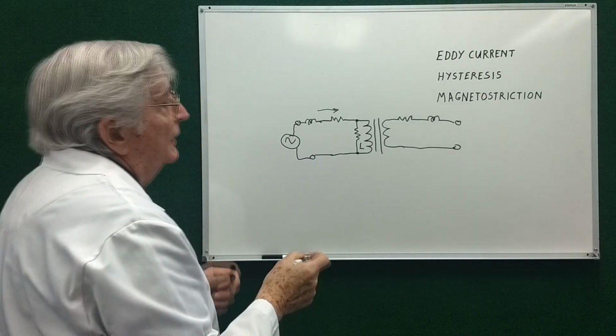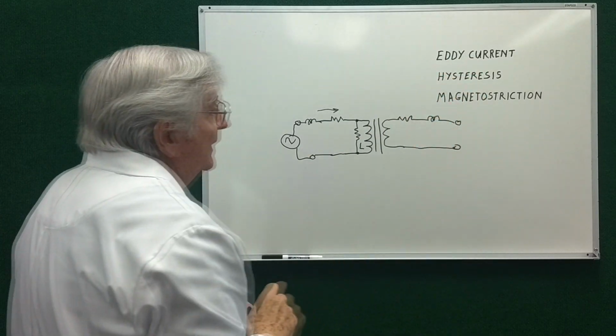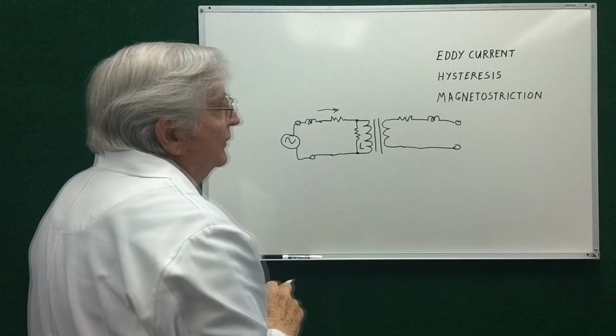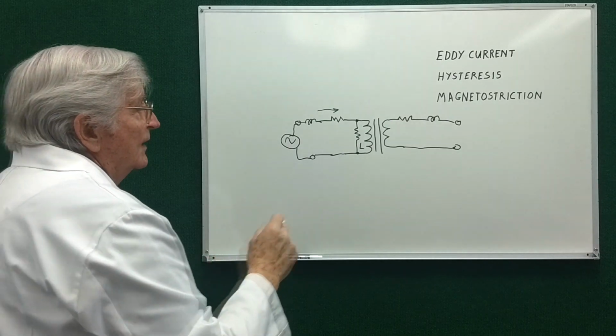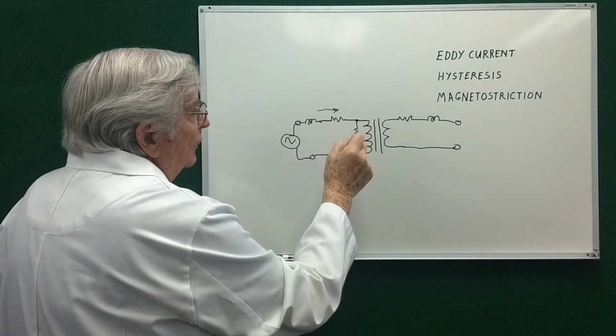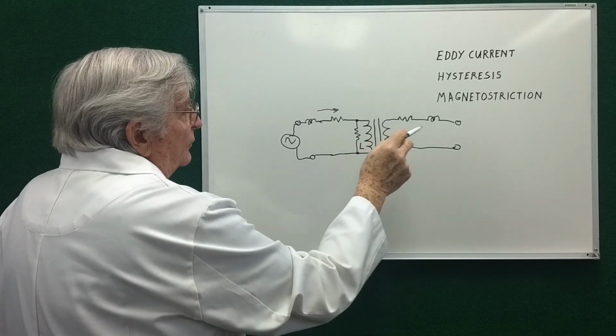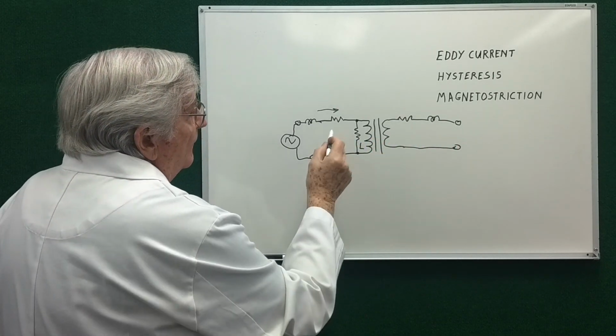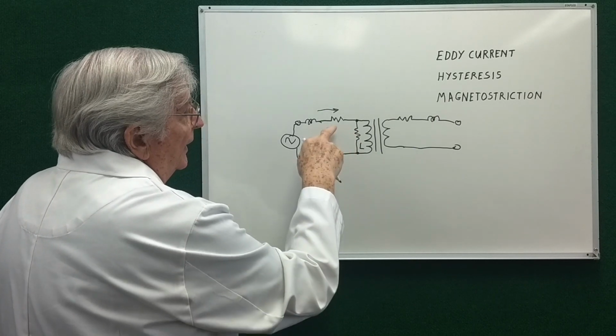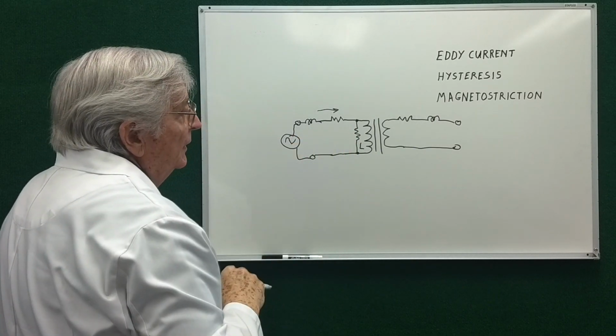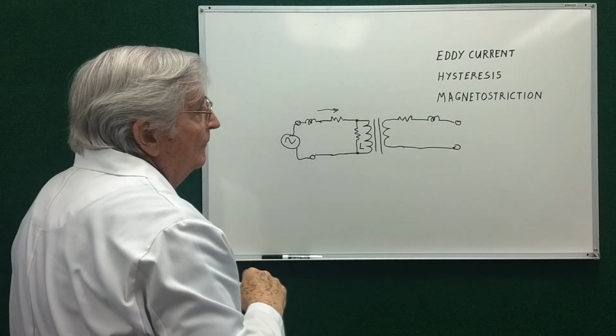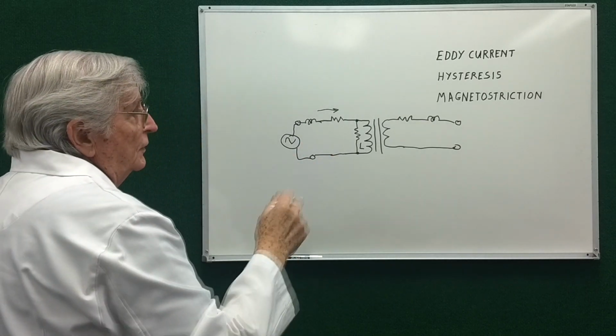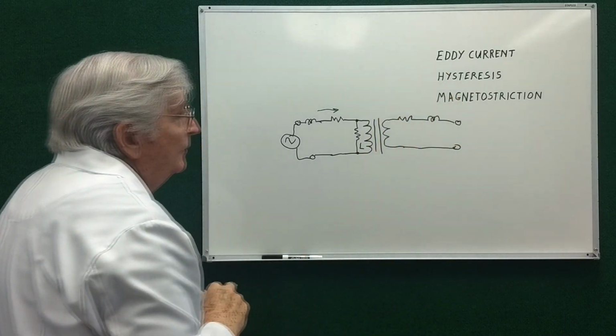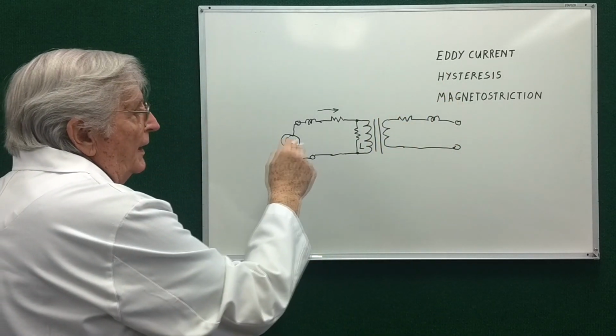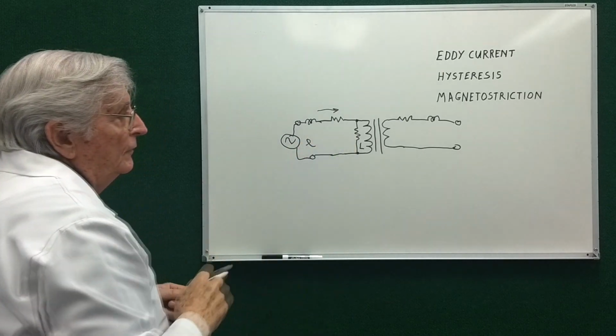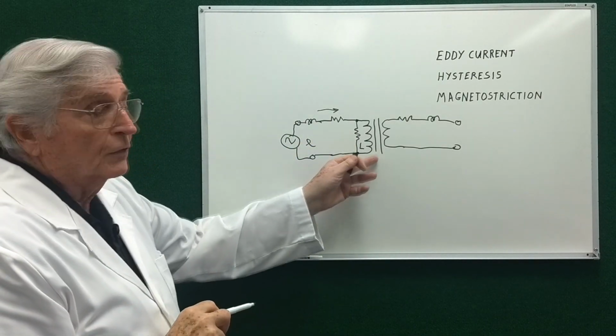So it turns out these losses here are maximum when there's no load on the transformer. And that's because the voltage across this coil is maximum. As we start to load the secondary, the primary current will go up, and we'll get more of an IR drop across that resistor. So it doesn't change very much, but just applying the voltage to the primary makes the core start to work.